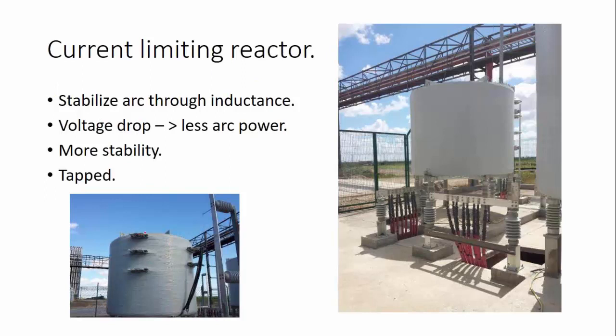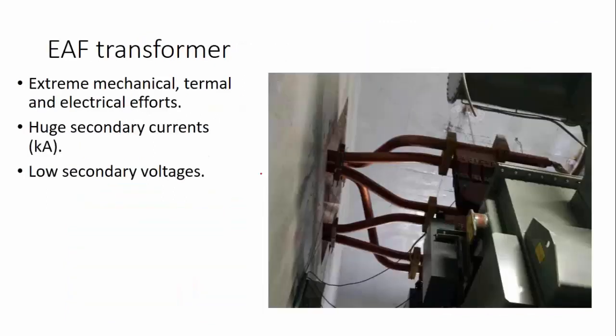This reactor is tapped. You can see that you can connect it in many positions. This reactor has 1, 2, 3, 4, 5 taps, depending on the operating conditions. Now, normally, when an electric arc furnace facility is designed, they do not know for certain how the furnace will operate. So they let the reactor be changed to match the operating conditions, both actual and desired. So that's why it has taps.